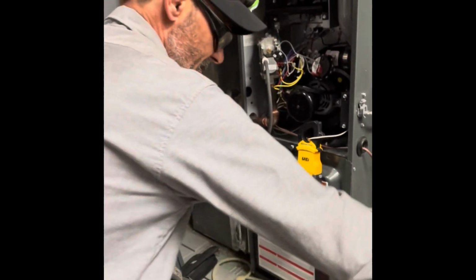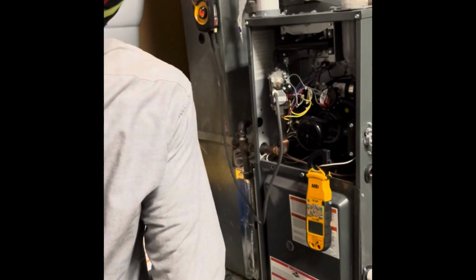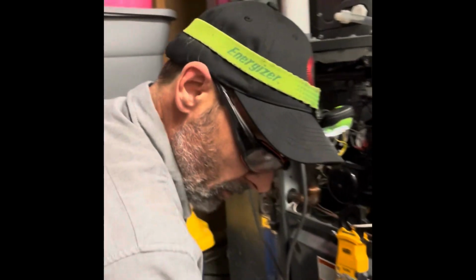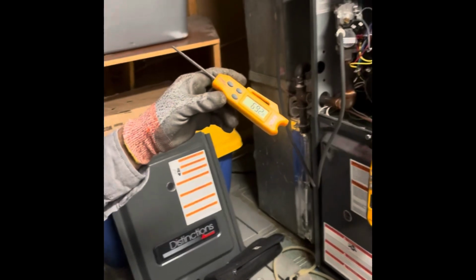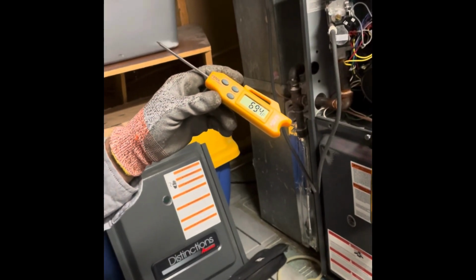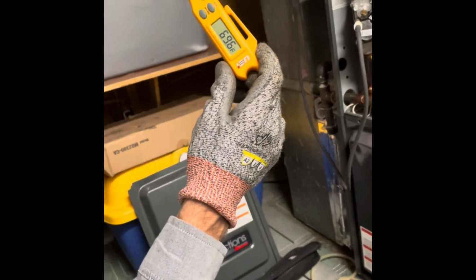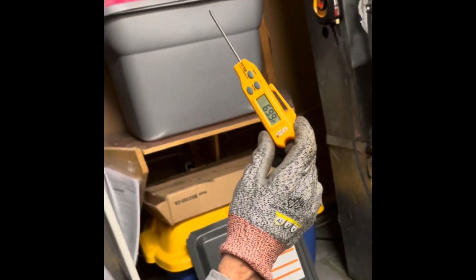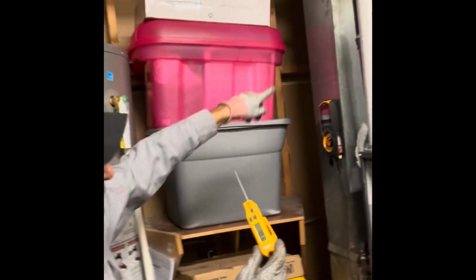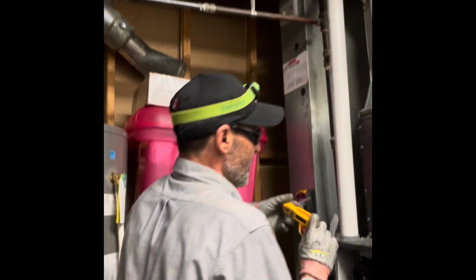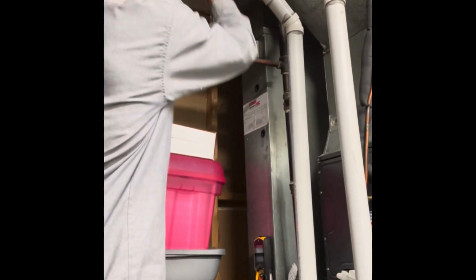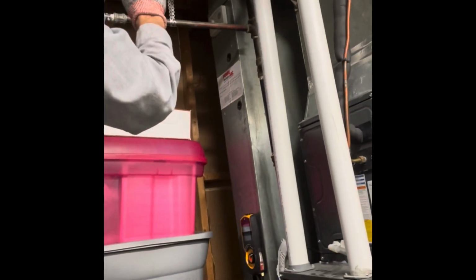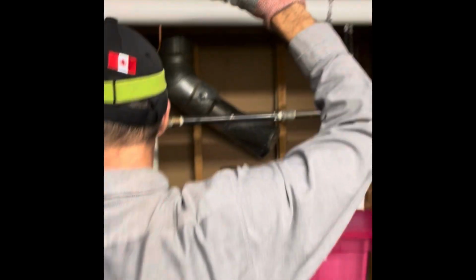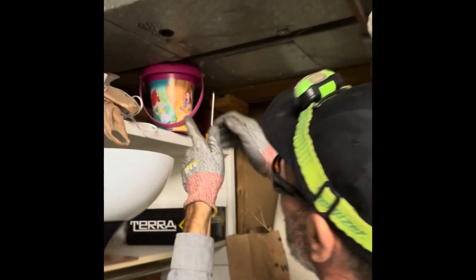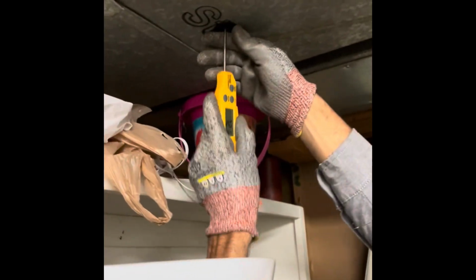In the meantime, I'm just going to get my temperature probes. I got my thermometer. Right now 69.4. I want to put this in our ductwork. I want to see what our supply temperature is, as well as our returning air temperature. So we'll start with our supply, and we've got to find a spot to put this. So a very good area is going to be a duct cleaning plug.